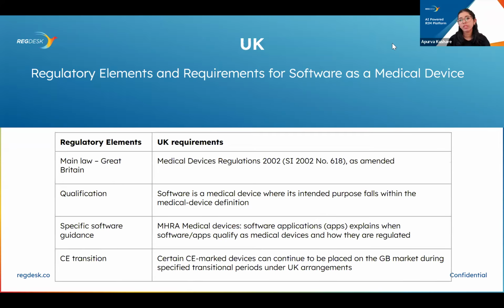And the next market that we will be talking about is the UK. So we have some regulatory elements here and also the requirements in the UK. So the main law in Great Britain is the MDR regulation 2002, as amended. And then the qualification part: software is a medical device where its intended purpose falls within the medical device definition itself. Specific software guidance here: MHRA has established some software application guidance which explains how software apps qualify as medical devices and how they are regulated in the UK.